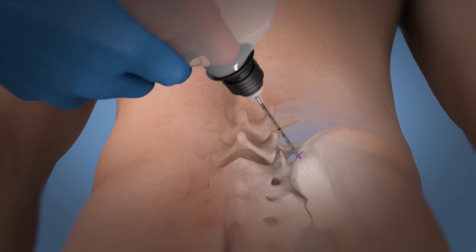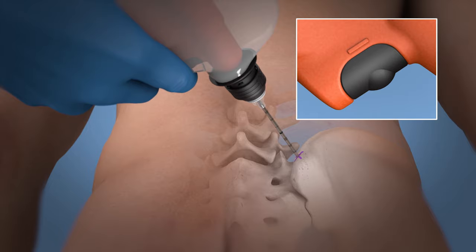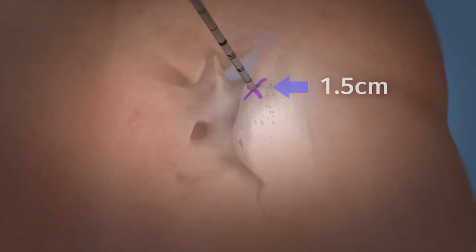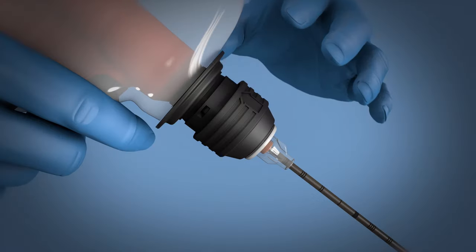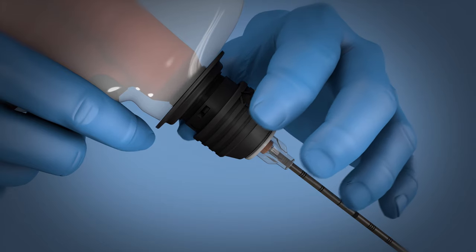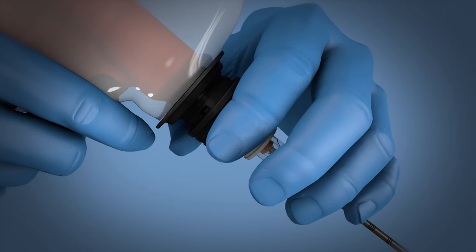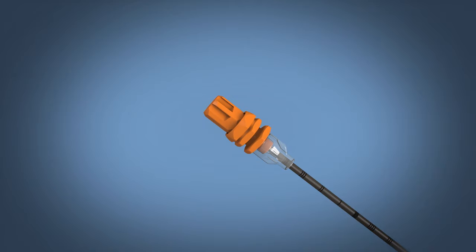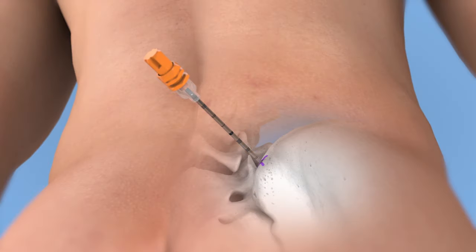Release the trigger when a change in resistance is felt or a depth of one to one point five centimeters is reached. Disconnect the driver from the needle by lifting up on the black collar on the connector and lifting the driver up and off the needle hub without dislodging the cannula.